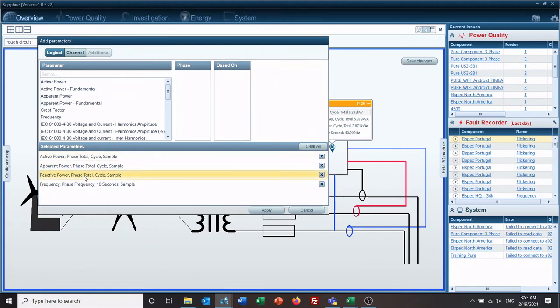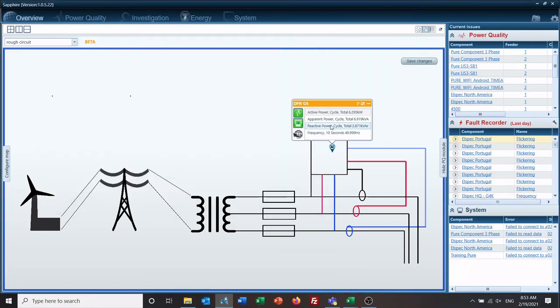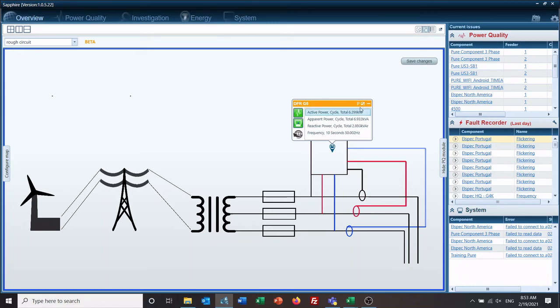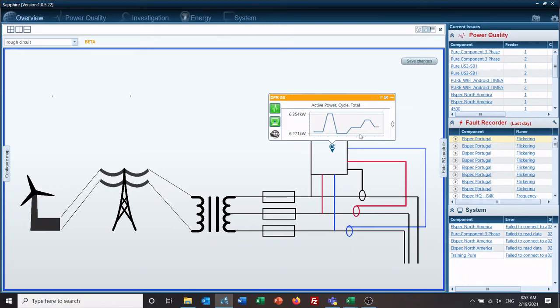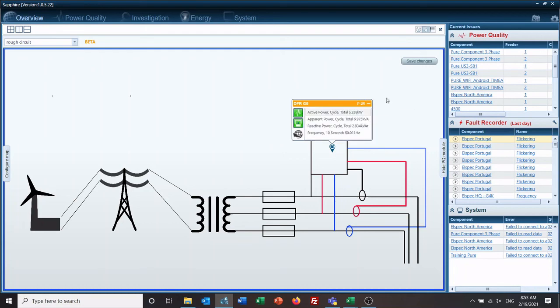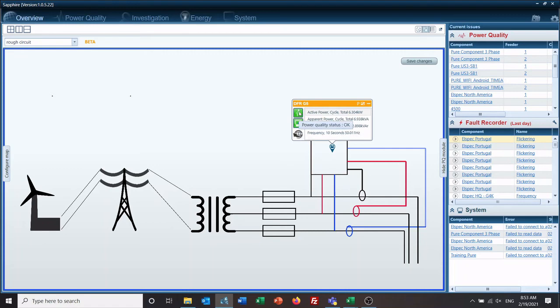Parameters: active power, apparent power, reactive power, frequencies are all here. We could add or remove any of those at any time. We can click on active power, show a small chart, removes the chart, go to the device's website. Tell us we're recording data, our status is good, our power quality status is okay, we don't have any violations currently.